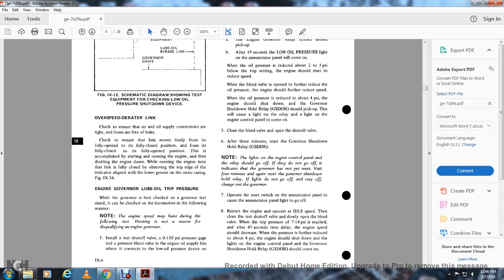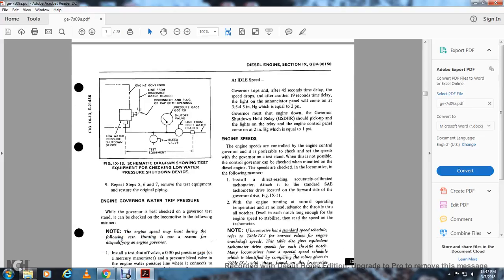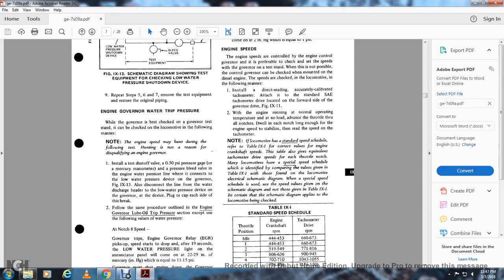When the pressure is further reduced to about 4 PSI, the engine should shut down. The lights on the engine control panel and the governor shutdown hold relay should come on. Figure 9-13 is a schematic diagram showing test equipment for checking the low water pressure shutdown device. The engine governor's low water pressure shutdown device is tested by disconnecting and capping both openings of the water discharge line, while the other end of the test equipment (bleed valve, pressure gauge, shutoff valve) is attached to the line from the inlet on the water header.